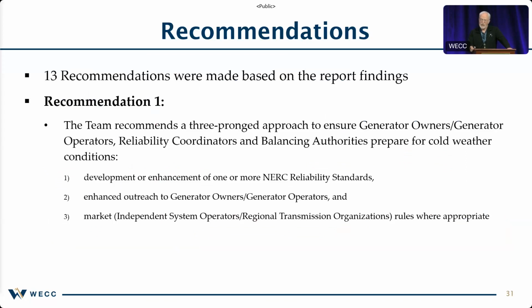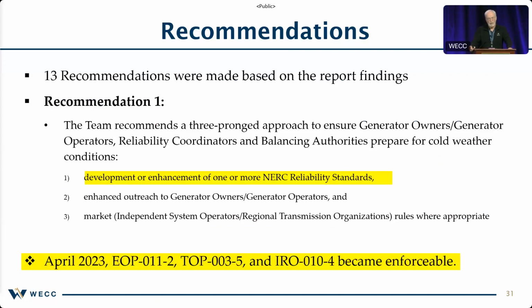So some of the recommendations they did, 13 recommendations for this report. Of note, development and enhancement of NERC reliability standards. So 2018, after the years of different recommendations for cold weather mitigation measures to be put in place, it finally gets to the point where cold weather standards have been identified to be the solution for the problem that we're seeing. In 2023, these cold weather standards that were part of the 2018 event recommendation became standards, EOP-11-2, TOP-3-5, and IRO-10-4. So a long period of time was kind of talked about time frame today, especially talking about IBRs. How long is it going to take to get these standards in place? In this particular case, many, many years before standards were put in place for the cold weather.